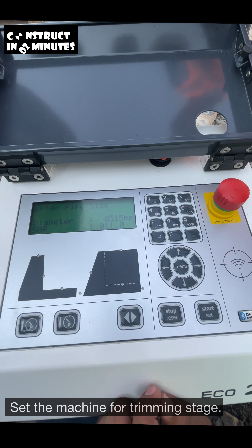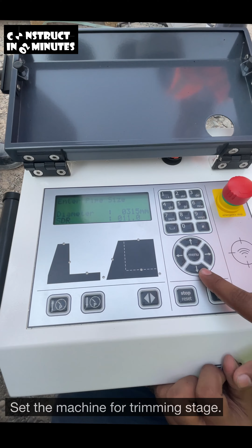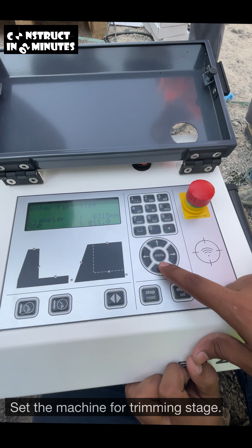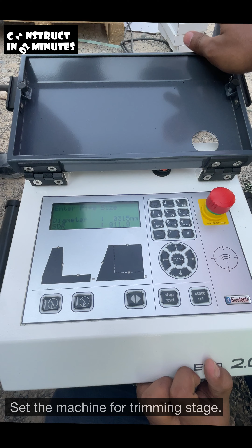What is SDR? What does it mean? SDR is the ratio of the diameter and the wall thickness, diameter to wall thickness. It's always written on the pipe. SDR means standard dimension ratio. If you know the wall thickness, press the down button. It changes to wall thickness. Again press, it converts into the SDR. Both are always written on the pipe.